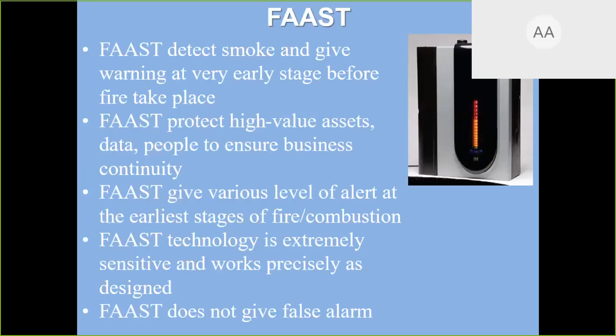FAAST detects smoke and gives a warning at a very early stage, before the fire takes place, because the smoke will come out before the fire. FAAST protects high value assets, data and people to ensure business continuity. FAAST gives various levels of alert. It has 5 sensors depending on the smoke density, whether it is gas, paper, wood or oil. All smoke has different density, and it will give you an alarm based on which type of fire there is. So it will give various levels of alert at the earliest stage of fire or combustion. Earliest stage means before combustion takes place.